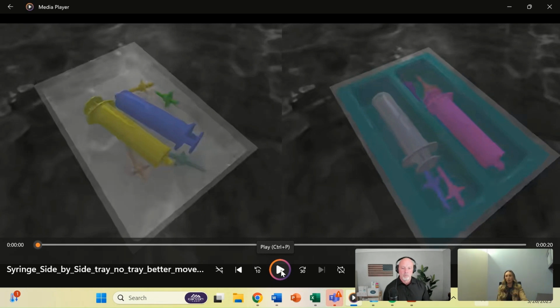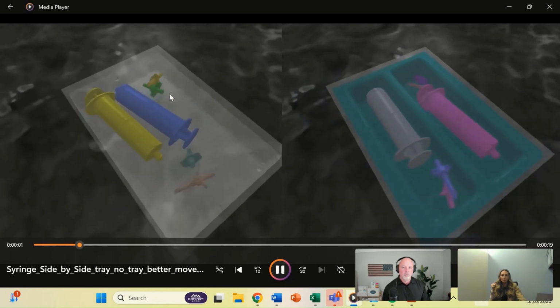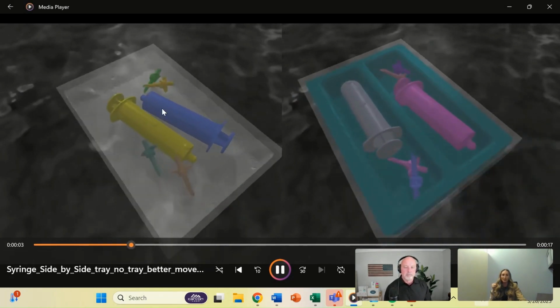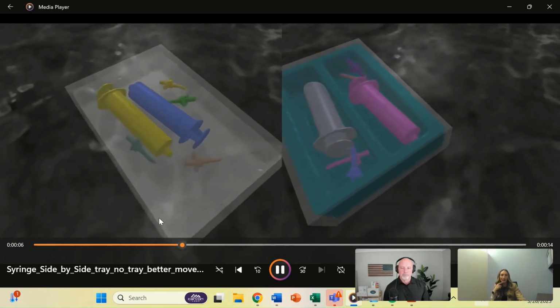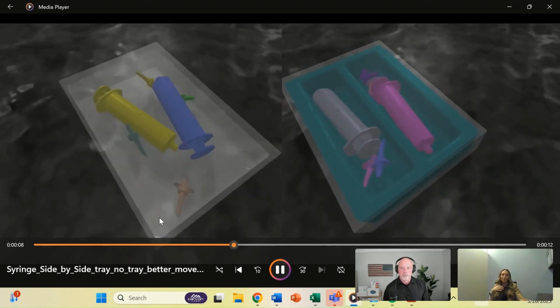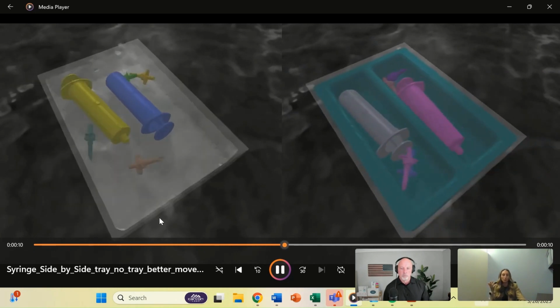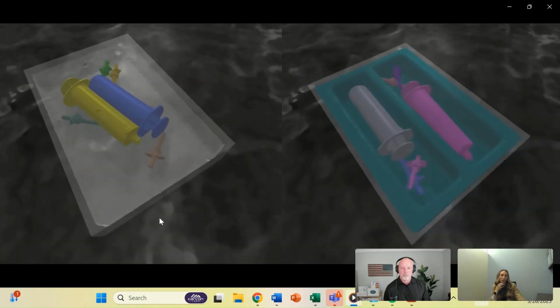And then you go to vibration. Drops and vibration are your two biggest dynamic forces that cause failures in packaging. With drops, you could see if this was just shaking around—maybe when you drop it, this syringe slams into the side of the tray and that causes a crack. So that's probably one of your most common failures in drops.